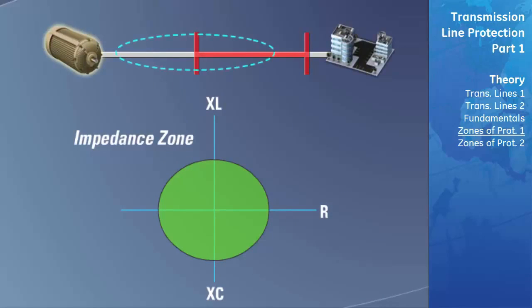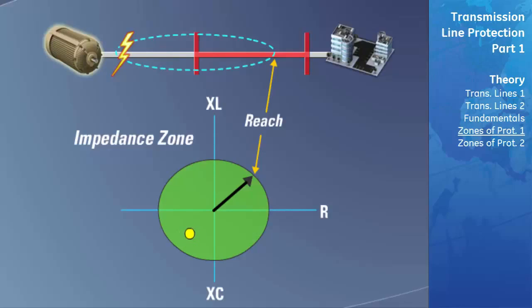First, we will discuss the zone of protection known as an impedance zone. Any impedance that falls within the radius of the circle indicates a fault that needs to be cleared. The reach indicates in ohms how far down the power system the zone of protection extends. This type of zone is inherently non-directional and will detect faults that occur in the reverse direction away from the point of measurement. This type of zone is normally used for generator backup protection.